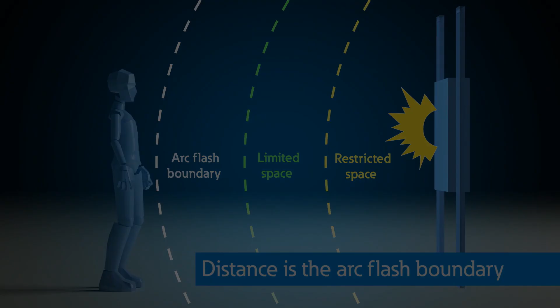So when you think about electrical safety, there are basically three different types of hazards. You have your shock, arc flash, and arc blast. I always lump arc flash and arc blast into one topic. So you have shock and arc flash. Both of those are just as critical as the other. I mean, they'll both kill you. And as designers and as electrical contractors, we've got to be thinking about the individual who's going to be working on this equipment. We want to prevent them from accidentally coming in contact with something that's energized, which will help prevent shock and also help reduce the likelihood of having an arc flash event.